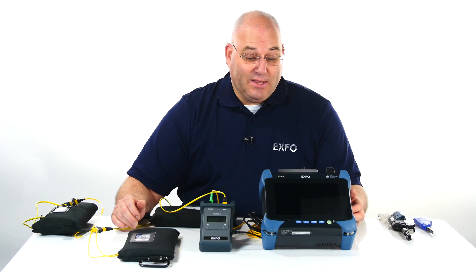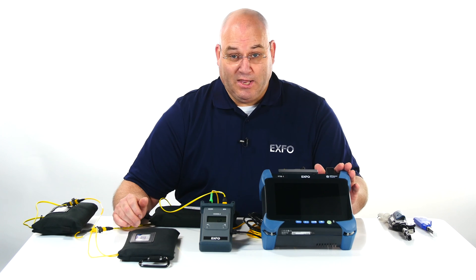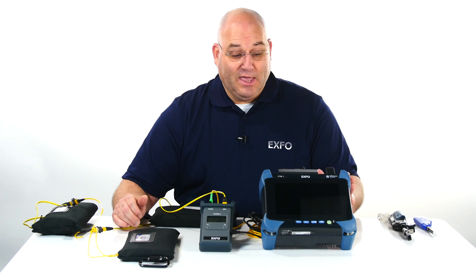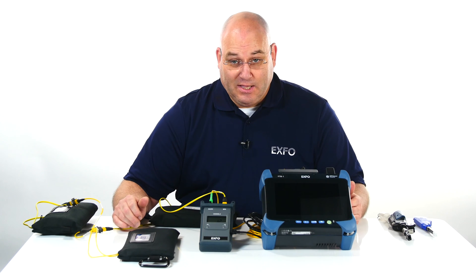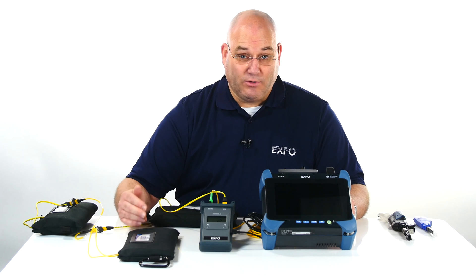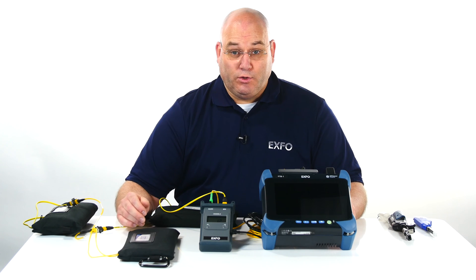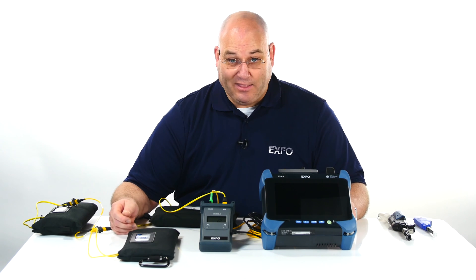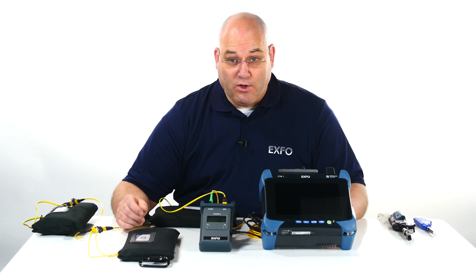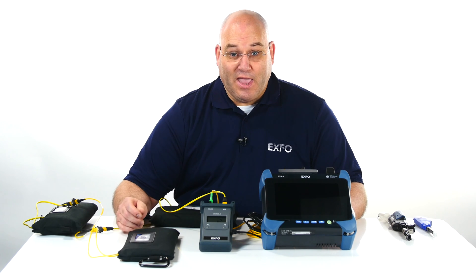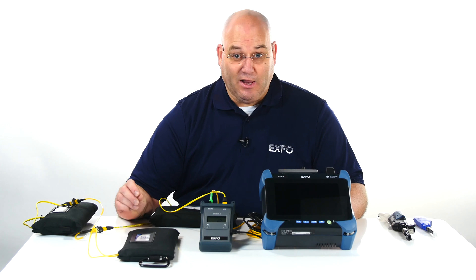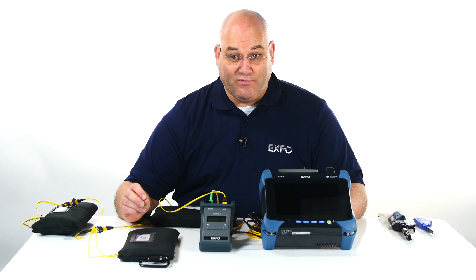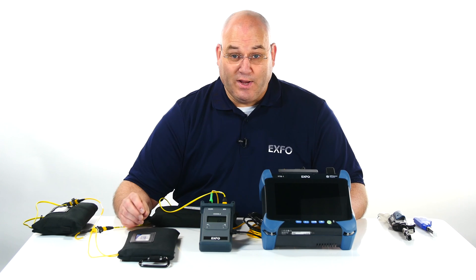The ability to use an OTDR IOLM gives you the possibility inside a fiber optic network of a data center or enterprise to measure the link length, link loss, link ORL, and also being able to position and allocate loss and reflectance for each and every specific event, being a splice, connector, or fault present on this fiber optic network at the test wavelength of choice.